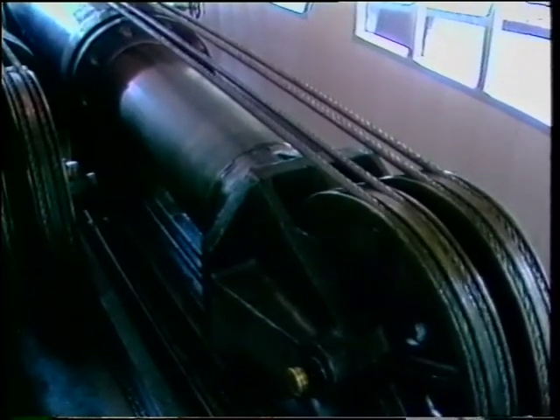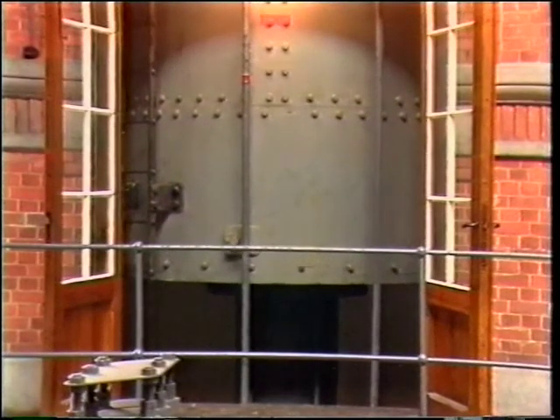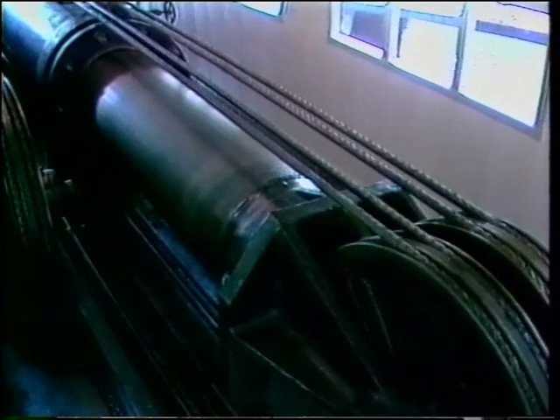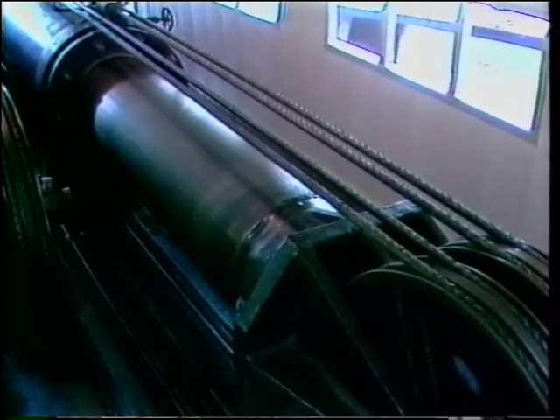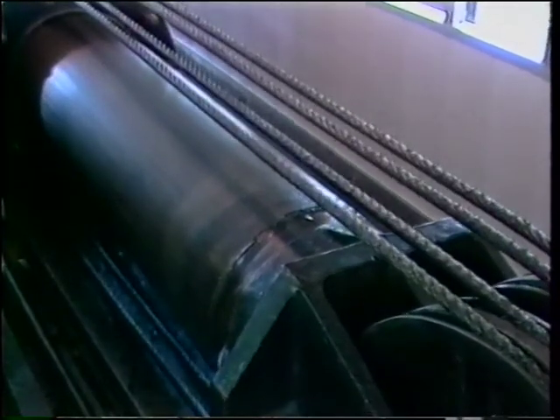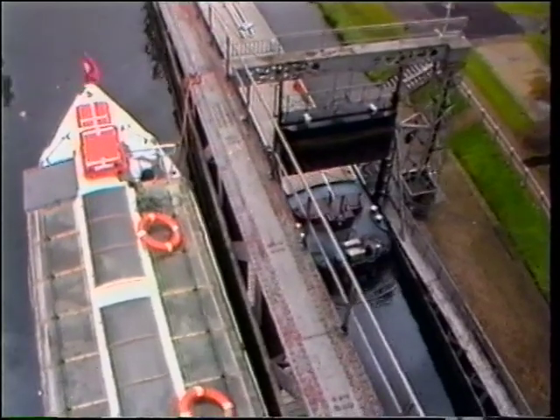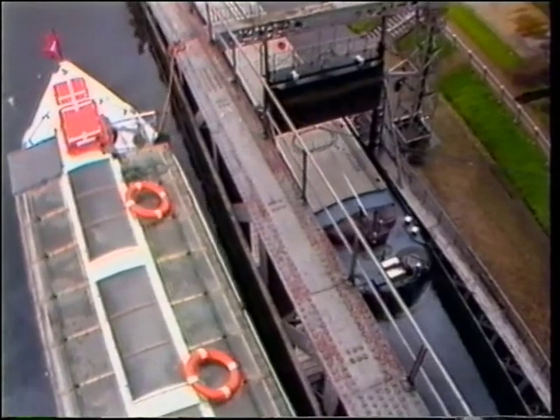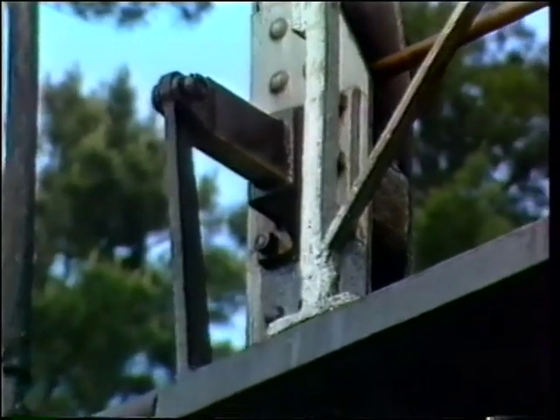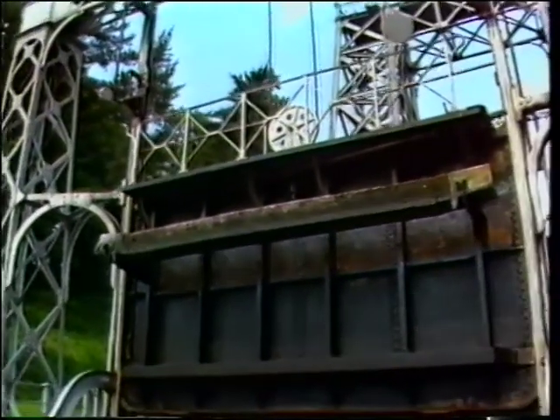At the same time, the accumulator falls in its tower. A wedge is then put in place to secure the gate, so that the boat does not have to pass under a 25-tonne gate hanging from a single cable. Once this is in place, the pressure can be decreased and the cable goes slack. Boats can then enter or leave in safety. To shut the gate, it has to be lifted up slightly so that the wedge can be removed, then lowered again. The weight of the gate forces the piston back into the cylinder, and at the same time, the water which was used to create the pressure to raise the gate is sent back into the canal.